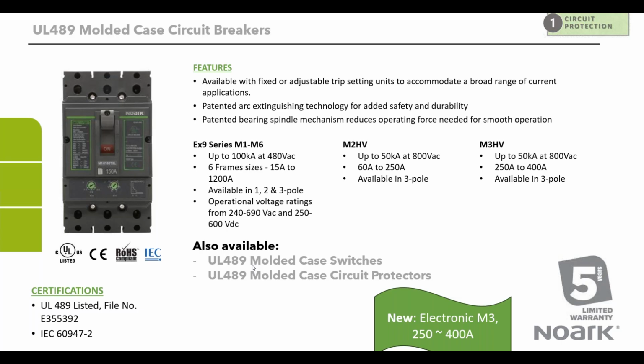The molded case protector is a device that is used for motor starting, and so it only has magnetic protection, so only for short circuit, and cannot do overload protection.